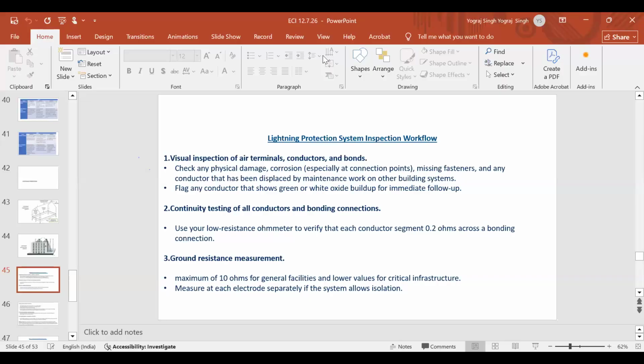The Bible of a maintenance engineer is that inspection, whenever it is done, must be recorded. Air termination must be checked for any physical damage, corrosion, missing fasteners, and any conductor that has been displaced by maintenance work. Now what happens? These things are provided on the rooftop. Somebody repairs the water supply line or the roof waterproofing, and they will disturb and damage your lightning protection system. So if that system is not healthy, and God forbid lightning occurs, it will fall on the building.